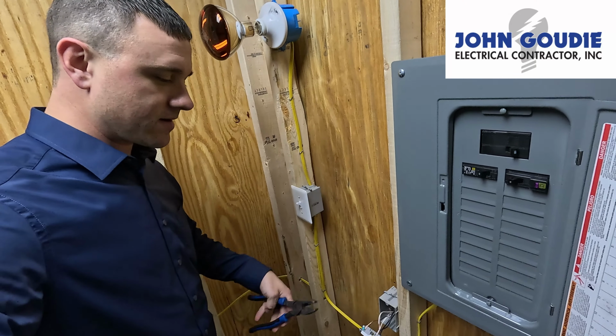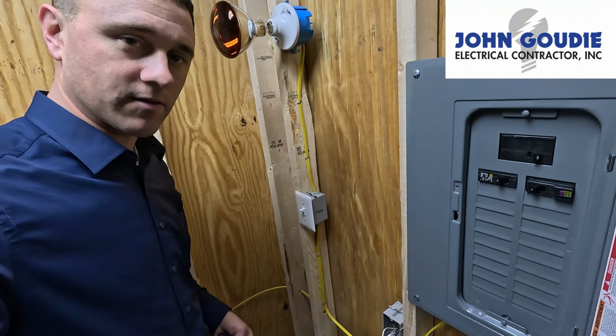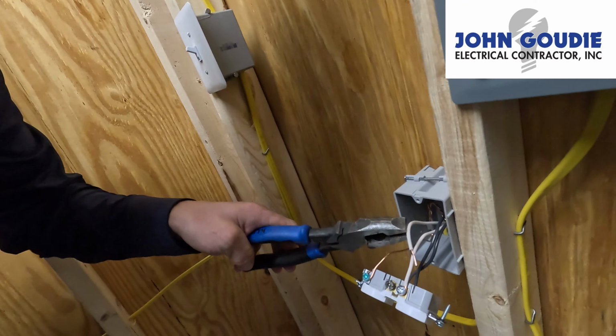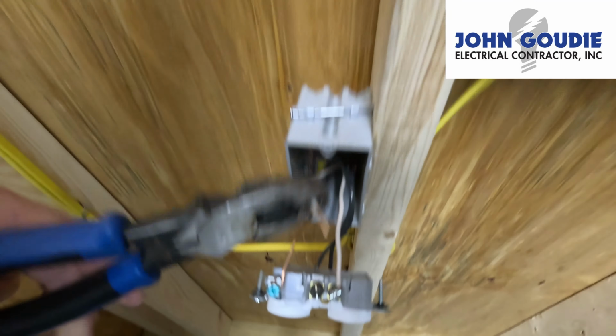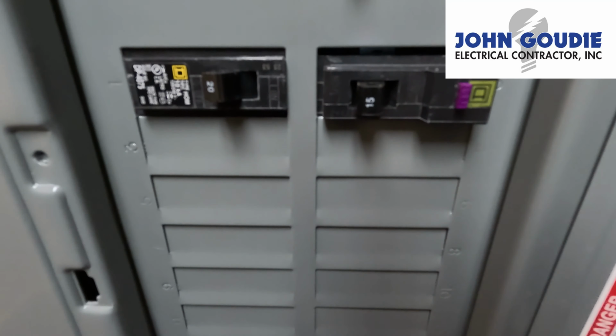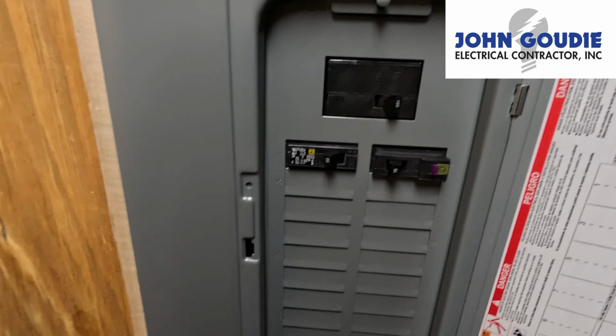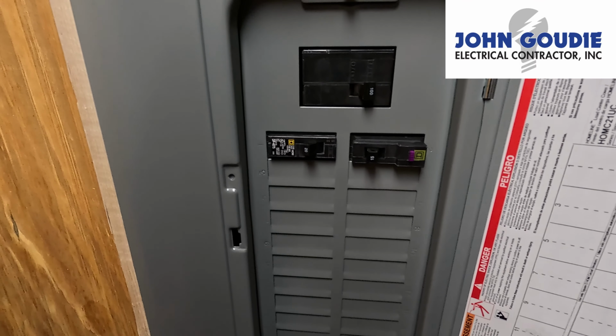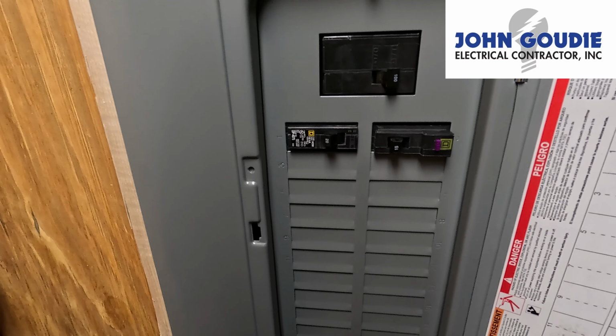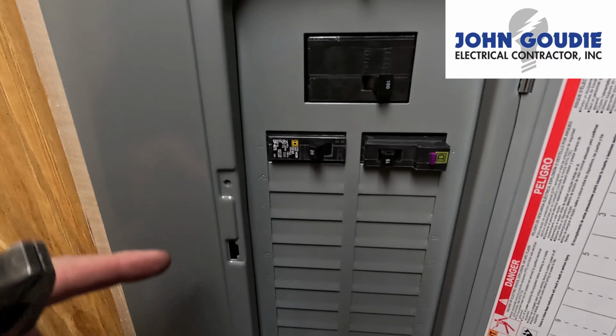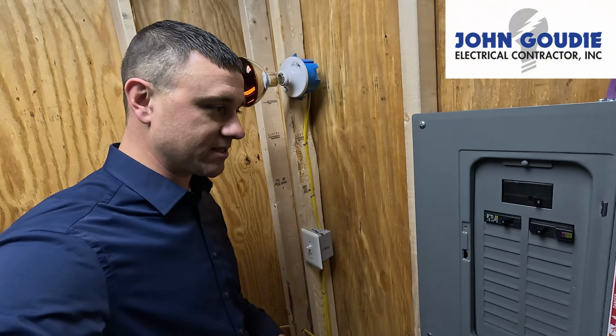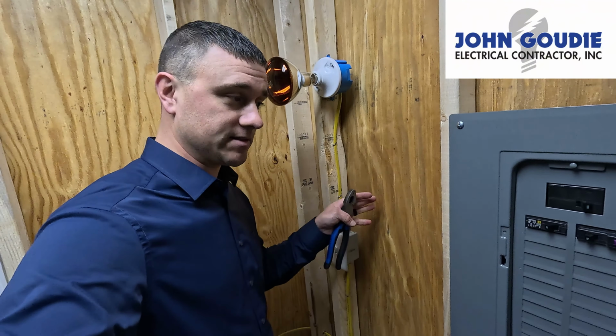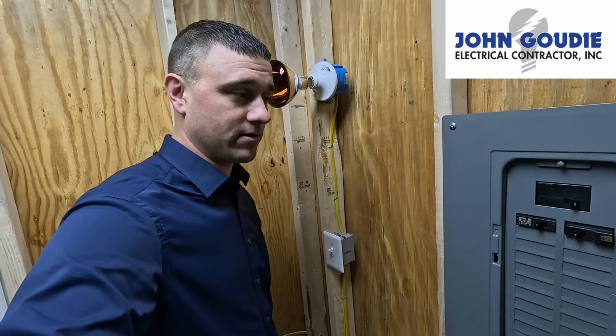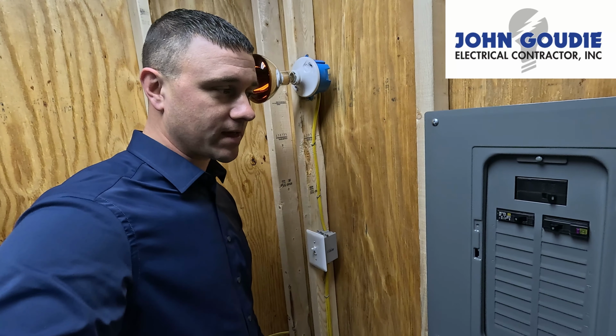All right, so now I've switched this around. Now I have this circuit tied into our arc fault breaker, and we're going to see what happens this time. So here we go. Our breaker trips when we have an arc, simulating any kind of arc we could have in the house. With this other breaker here, that could be arcing all day long, and that breaker is just not going to trip. It's not going to prevent a fire with any type of loose connection. It's just going to continue to allow power to flow through that circuit until either the connection breaks and disconnects the power, or a fire is started, and then it's just going to keep going. Where the arc fault breaker will detect that arcing and shut it off.